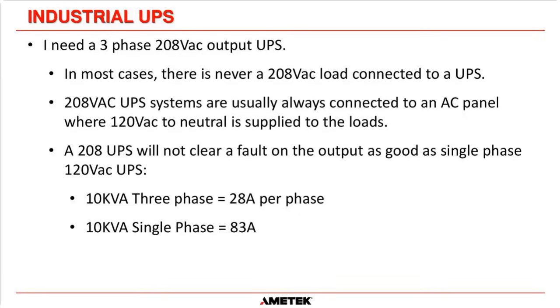So the first common misconception is, I must have a 3-phase 208 UPS output. That's absolute nonsense in most cases, because very rarely, I would probably say maybe 1% of the time, is there ever a 208 volt load connected to a UPS. Yes, there is a 208 volt distribution panel connected to most UPSs, but that 208 is then distributed as 120 volts to neutral. All the loads are 120 volts. So it's very, very rare that you ever need 208 volts. Okay.